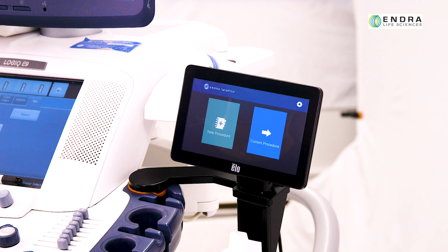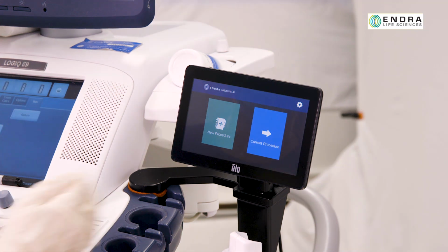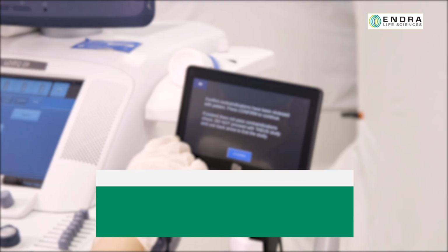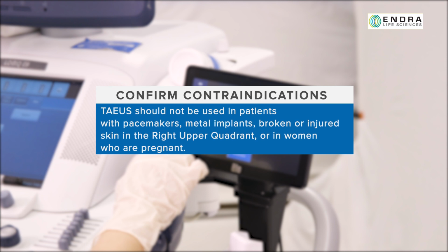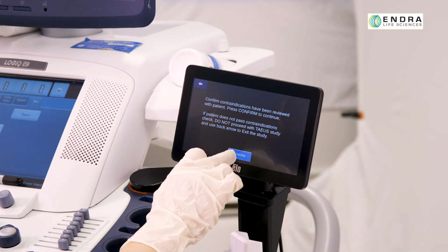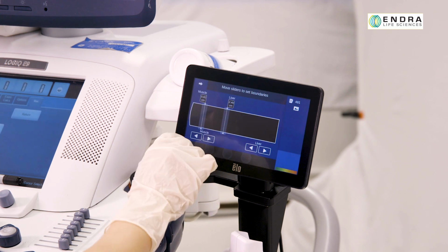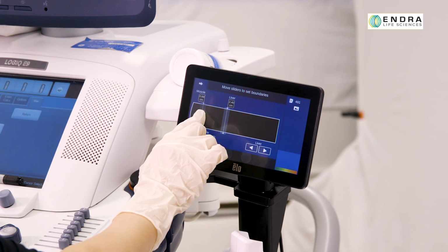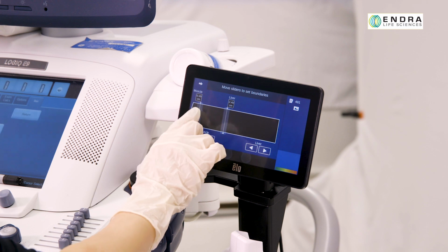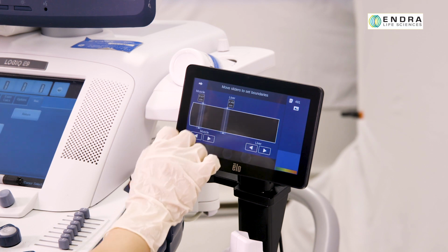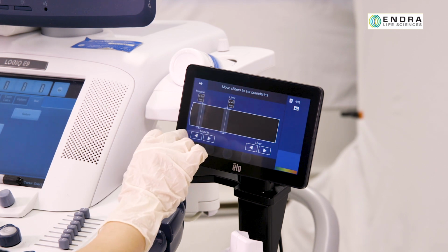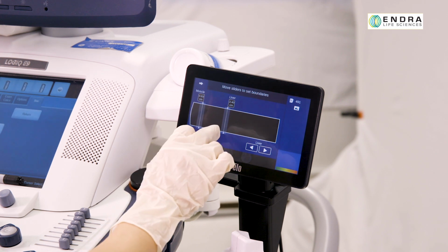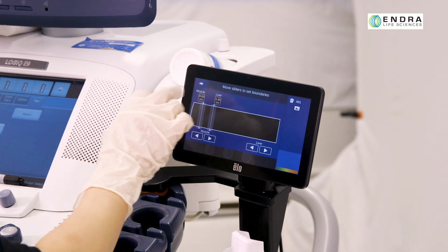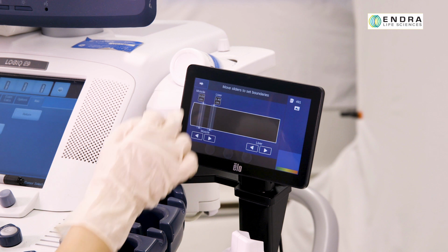We will now use the dedicated TAEUS software to start a scan. Tap the New Procedure button on the touchscreen monitor. Before proceeding, ensure that all contraindications have been reviewed with the patient, then press Confirm to proceed. On the next screen, drag each of the two slider bars so that the distances displayed correspond to the muscle and liver distances obtained from the B-mode image. Press the arrow keys for fine positioning adjustments. Then press the arrow icon to proceed.